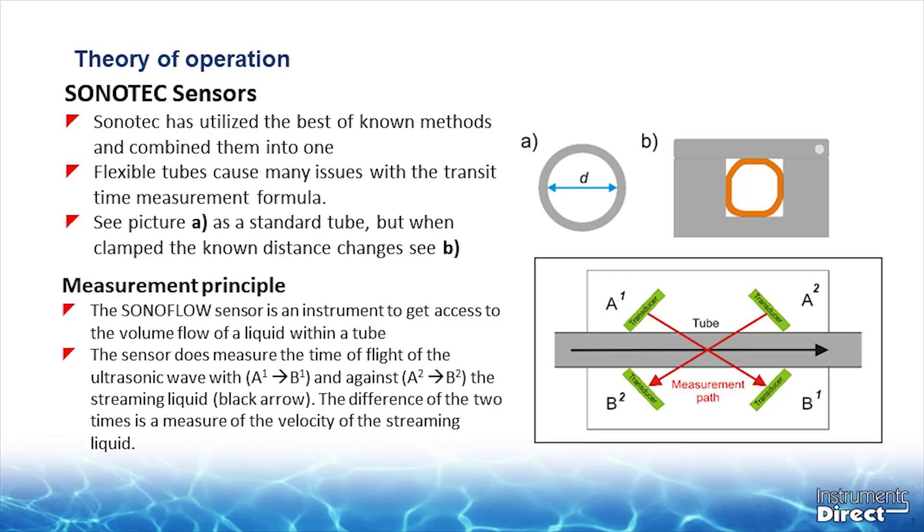The Sonoflow sensor utilizes the ultrasonic transit-time method. This transit-time math equation requires a defined distance across the pipe, or in this case, the flexible tube. Now the problem with a flexible tube is that the shape is not perfectly round or consistent in any way, so the math will not work.